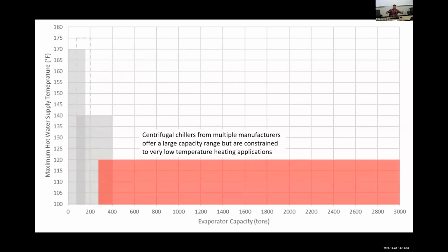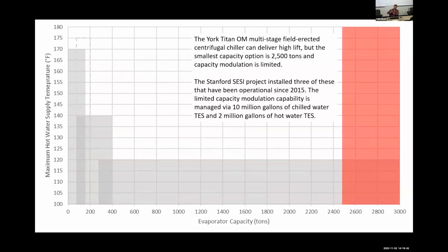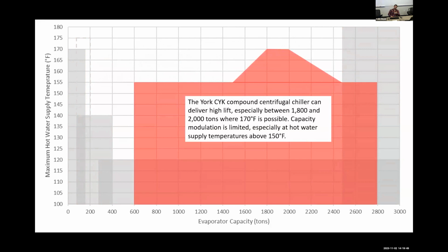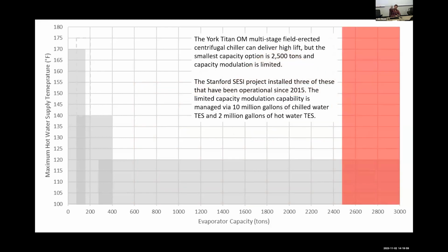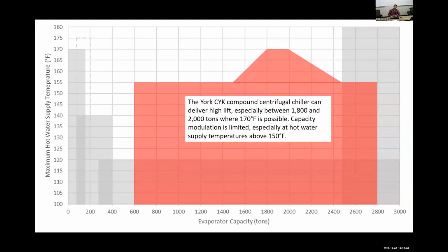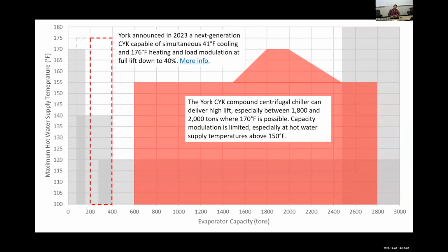There have been a lot of large centrifugals that can only do low lift. There have been large centrifugals like Stanford has that are very large that can do high lift. And then there's 2 other pieces that I wanted to highlight. The York CYK is something we've been considering at UC Davis, and it fills a lot of this void in the middle. Because if you go back here, there's a large area in the middle where, in a large range of capacity, there's just not high lift equipment. So the York CYK fills that area.